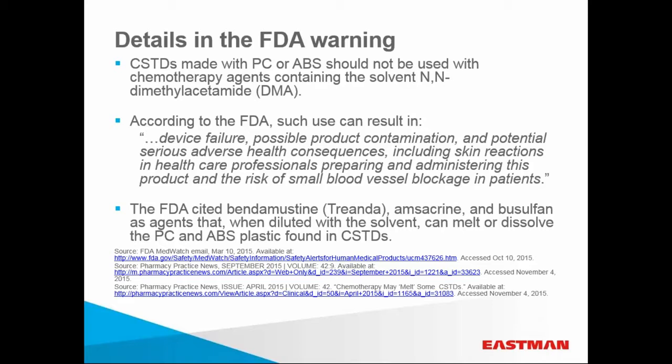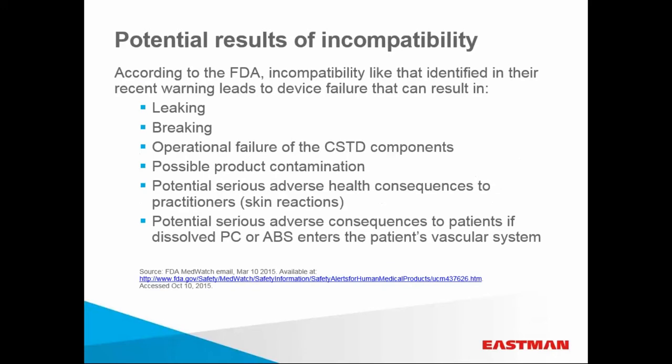This specific FDA warning generated a significant amount of healthcare industry press, as clinicians identified specific lists of devices that can and should not be used with Treanda. In addition to Treanda, the FDA also identified amsacrine and busulfan as other agents that, when diluted with DMAC, can melt or dissolve the PC or ABS found in closed system transfer devices. The FDA went on to require labeling changes for these compounds to more clearly warn clinicians about their drug delivery device choices. The potential results of this drug-device incompatibility can be serious, including potential drug product contamination, leaking product causing potential health consequences for practitioners, and potential serious adverse consequences to patients if dissolved PC or ABS enters the patient's vascular system.